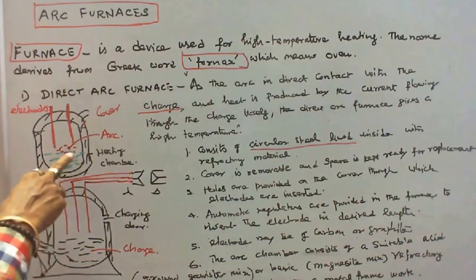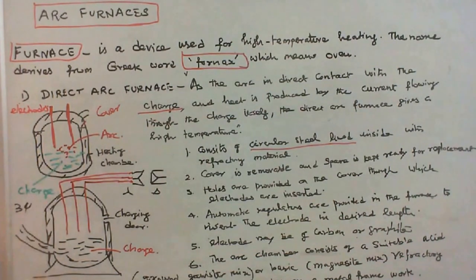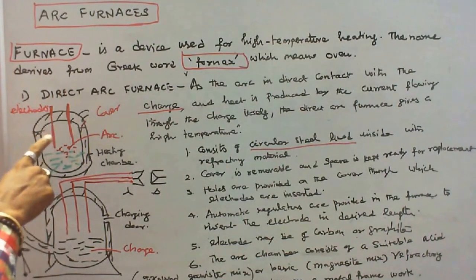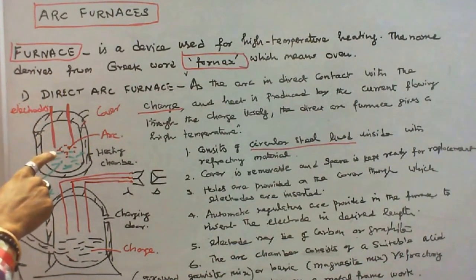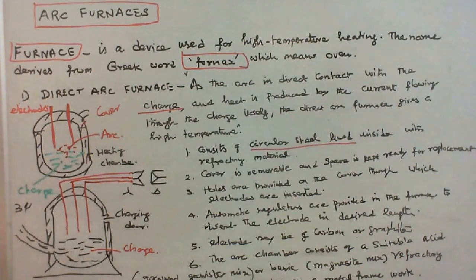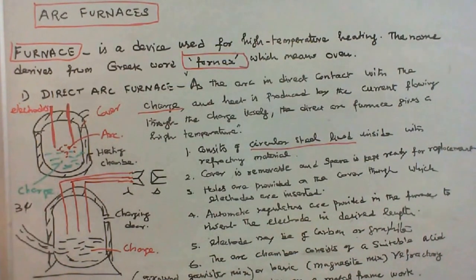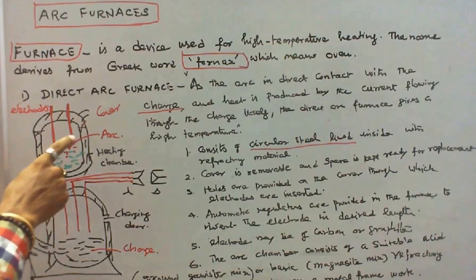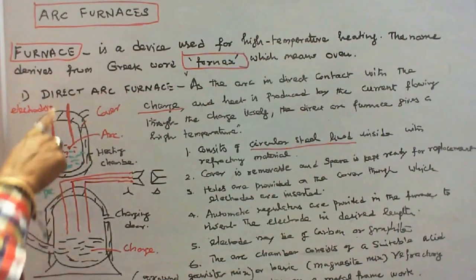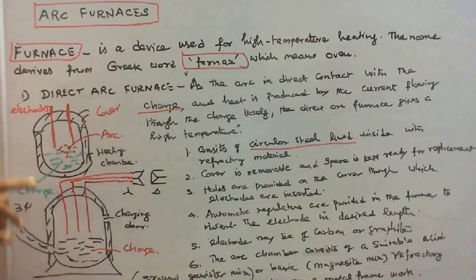The direct arc furnace gives high temperature. The direct arc furnace consists of circular steel lined inside with the refractory material. The top cover or roof is removable and spare is kept ready for replacement. Holes are provided on the cover through which the electrodes are inserted.